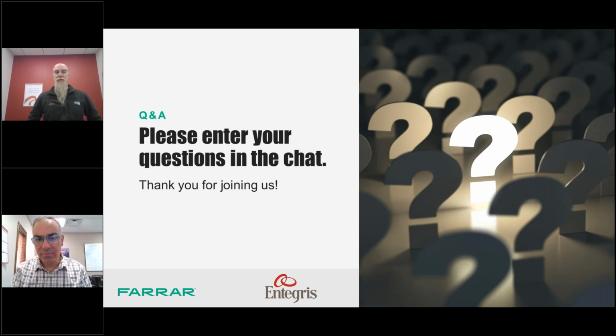That was really one of the first questions we had when we saw the different offerings in the 4000 series. We walked through some of the architectural plans for our Life Sciences Technology Center. We found we were taking over a space previously occupied by another lab, and even though we had good air exchange, when we did the math and calculations for heat load on one of the air-cooled chillers, it would have overtaken some of the HVAC systems currently installed in the space. But in doing the math, we found we actually had excess capacity in one of the liquid chilling systems in the building. That allowed us to transition to one of the liquid cooled systems to better match the needs of our facility as a whole.